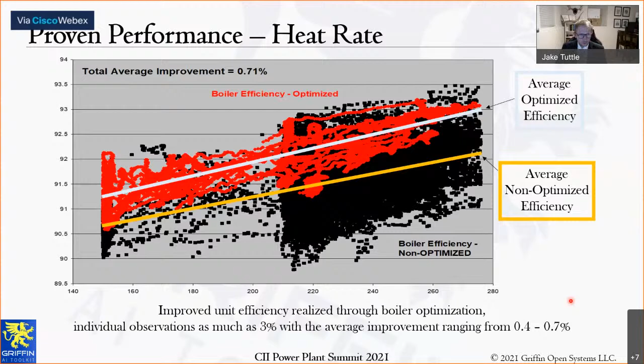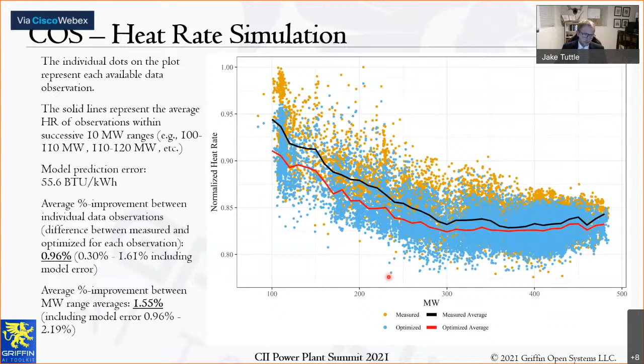Very quickly, I'll talk a little bit about heat rate as well. We're able to see improvements in overall heat rate on average in the range of 0.4 to 0.7% through just combustion optimization. We see as high as 3% in individual observations, but on average about that 0.4 to 0.7% range. In another project we've done, we were able to see similar results in actually minimizing heat rate itself across the load range. On average, about a 1 to 1.5% reduction in heat rate here through, again, simply combustion optimization. When you factor in components like soot blowing and cooling tower optimization, all those other features, that heat rate benefit increases.